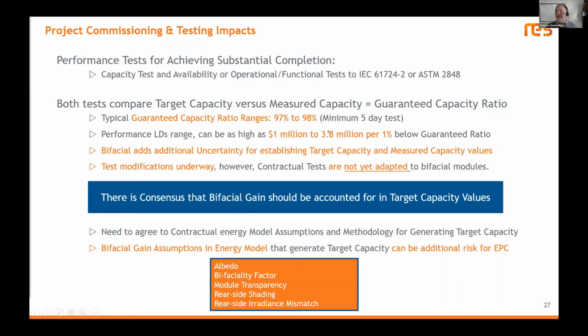You have to do a 5-day test to prove that ratio, but be very careful, because you risk liquidated damages between 1 and 4 million dollars per 1% below the guaranteed ratio.